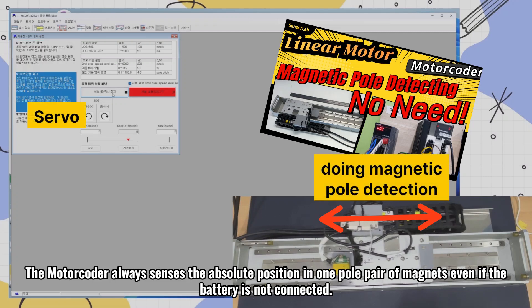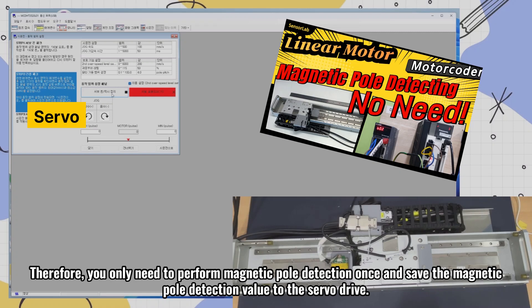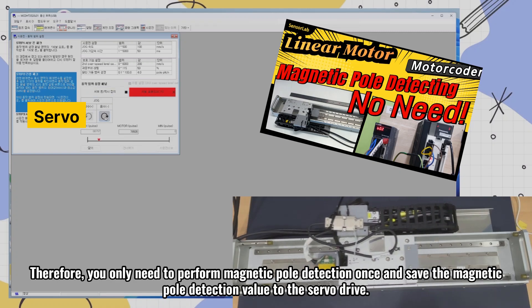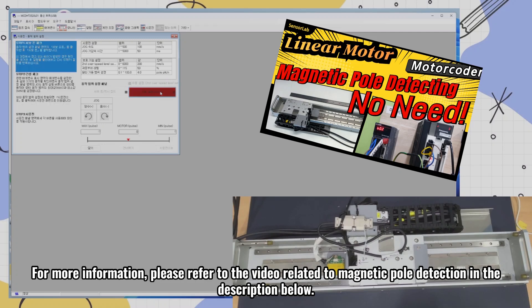The Motorcoder always senses the absolute position in one pole pair of magnets even if the battery is not connected. Therefore, you only need to perform magnetic pole detection once and save the magnetic pole detection value to the servo drive. You will not need to perform magnetic pole detection even if you turn the power off and on again. For more information, please refer to the video related to magnetic pole detection in the description below.